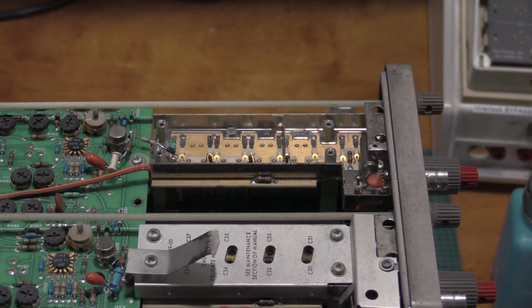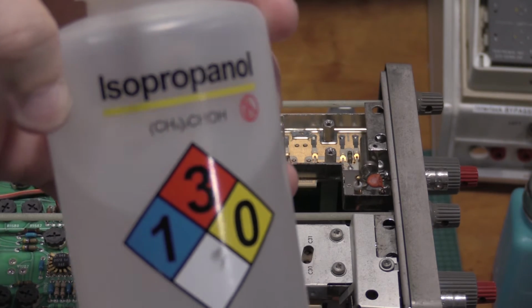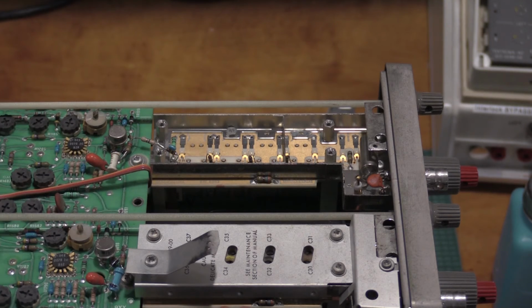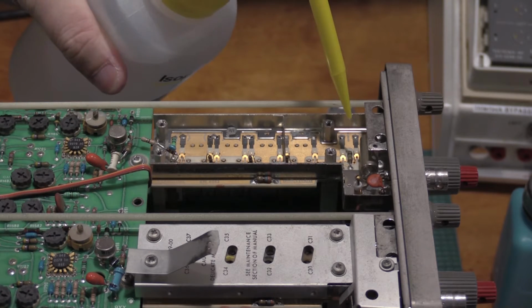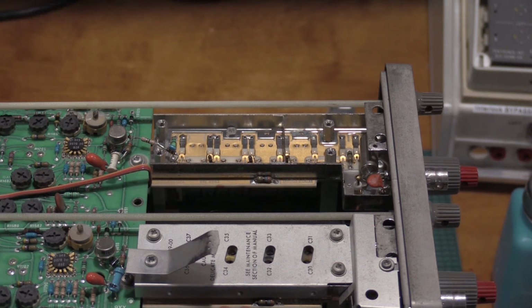This is a delicate board material, as called out in all of the Tektronix manuals, so do not use any harsh solvents on these. No contact cleaner, no nothing. And these contacts are supposed to be kept dry, so nothing that'll leave a residue. I'm using isopropyl alcohol. It's 99%. But we'll just flood the area with alcohol. Obviously, when you're flooding the area with alcohol, the unit is off.